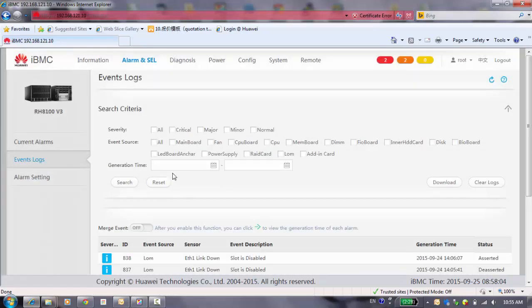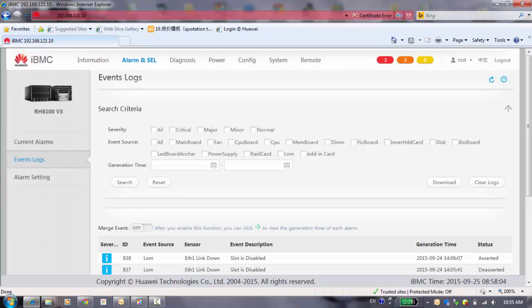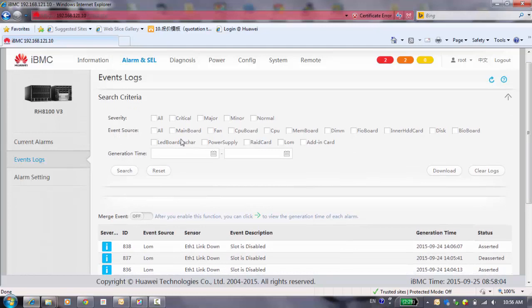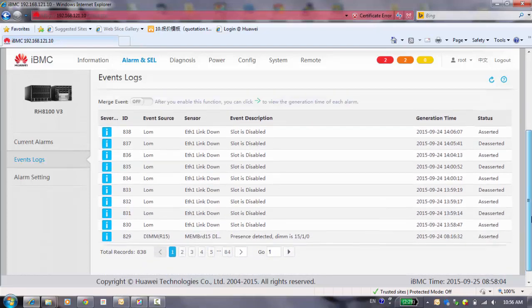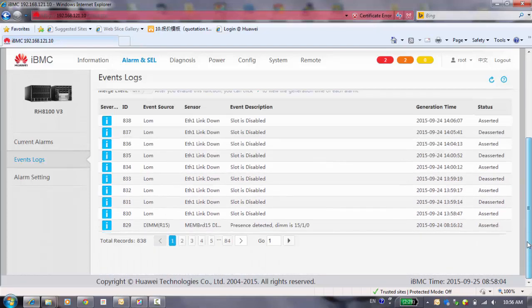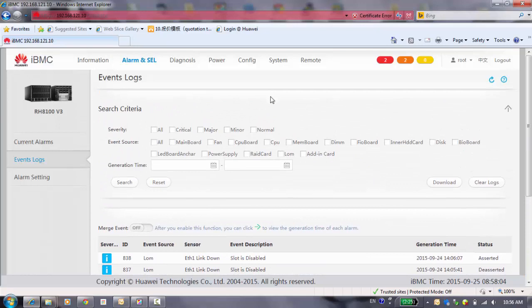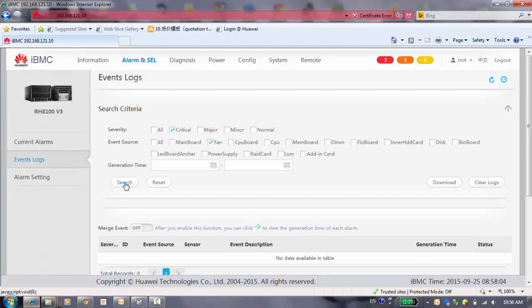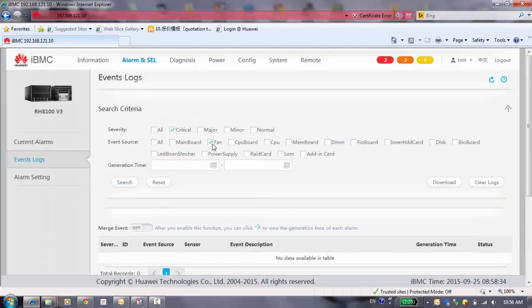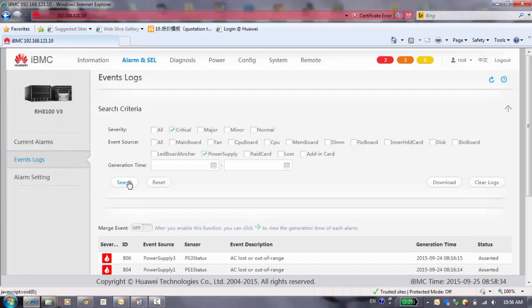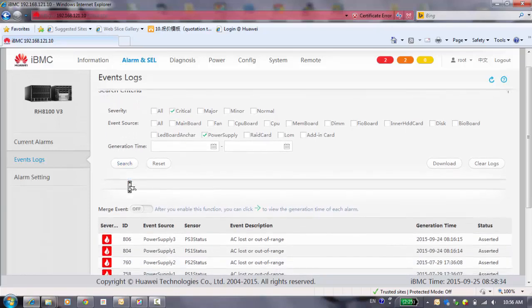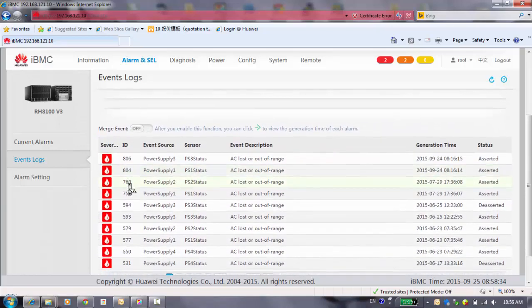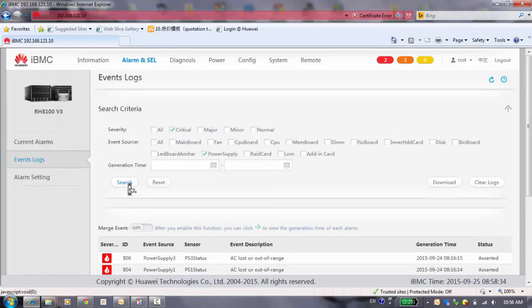And the event log. For this item, you can have a filter of the different kind of event. For example, maybe the event is too much for you, and you can't find some details which you want. You can choose and search here. For example, the fan and search. Here is no any available because the fan is working okay. And the power supply with the critical, you can see here you have some with the power supply critical.